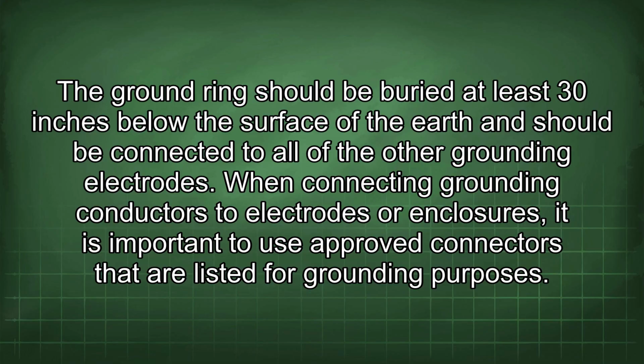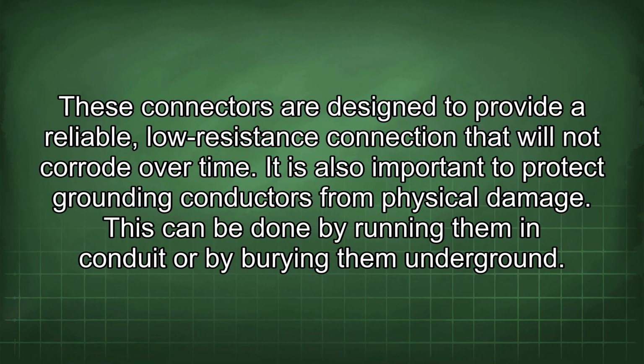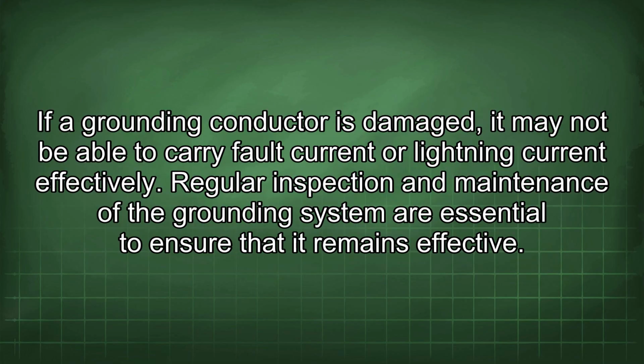When connecting grounding conductors to electrodes or enclosures, it is important to use approved connectors that are listed for grounding purposes. These connectors are designed to provide a reliable, low-resistance connection that will not corrode over time. It is also important to protect grounding conductors from physical damage. This can be done by running them in conduit or by burying them underground. If a grounding conductor is damaged, it may not be able to carry fault current or lightning current effectively.